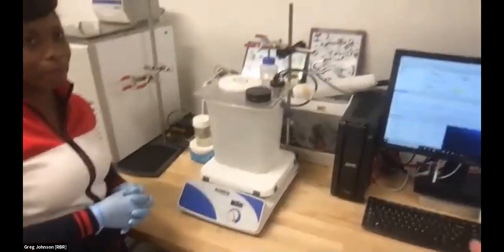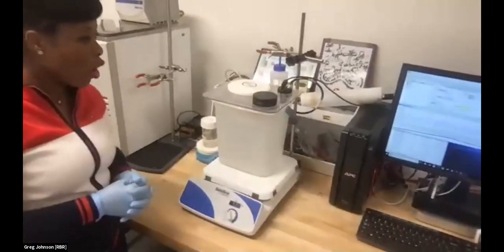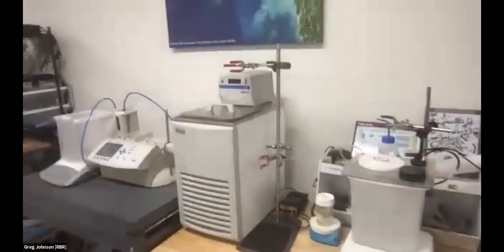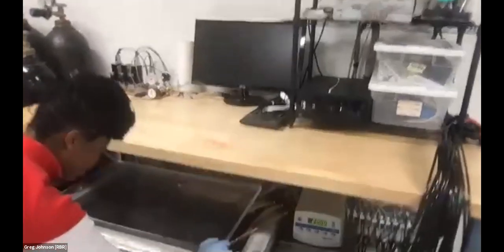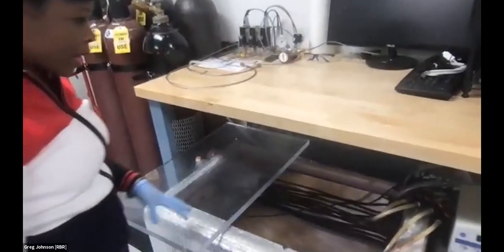So how do we do an optode calibration? We don't use just a bucket. No, we don't use a bucket. So over here, we have a bath. It's a huge bath filled with distilled water again. In there, we have two pumps to keep things circulating. We have these cables in there that end up pumping the gas in there. We have bubblers at the tip to spread it in. And we have cooling points in there too.